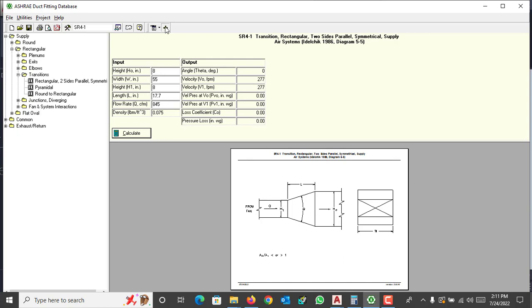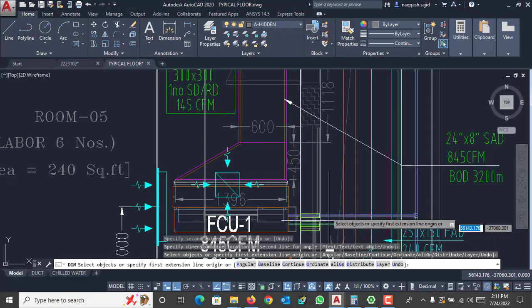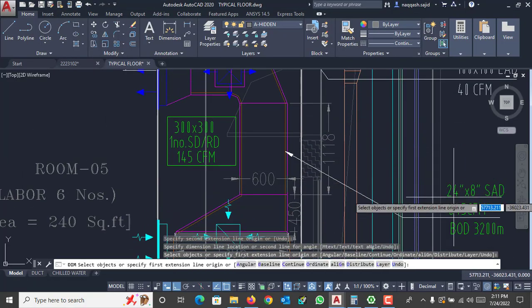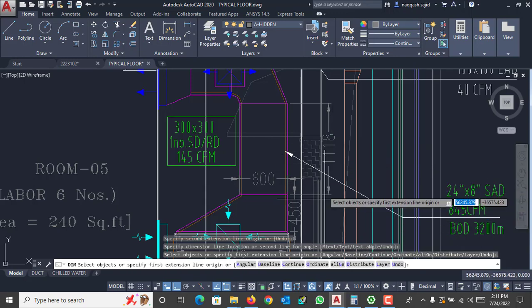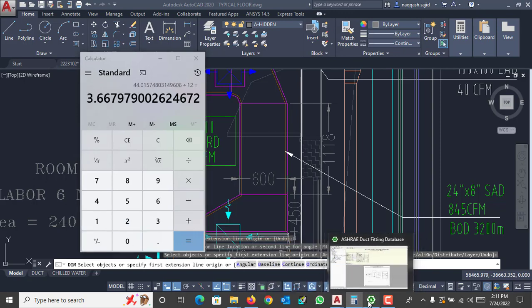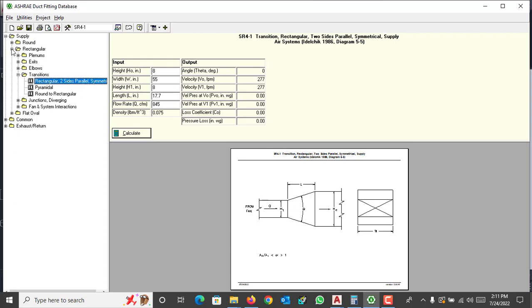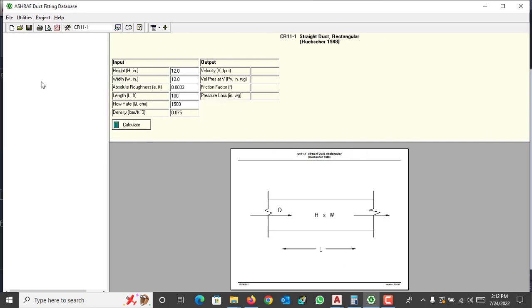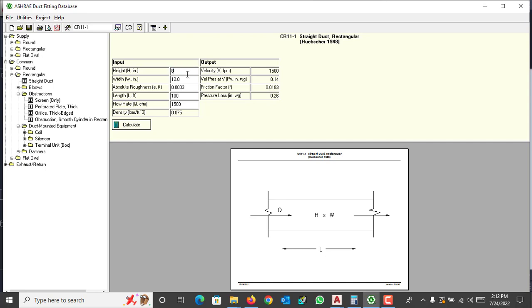Now we move to the straight duct. The straight duct is 24 by 8 inches, 845 CFM, and 1118 mm long which is approximately 3.67 feet. Select 'Straight Duct' from the common fittings. Enter height as 8 inches, width as 24 inches, length as 3.67 feet, and CFM as 845. Press calculate — there are also minor losses in this duct. Add it to your project for later.